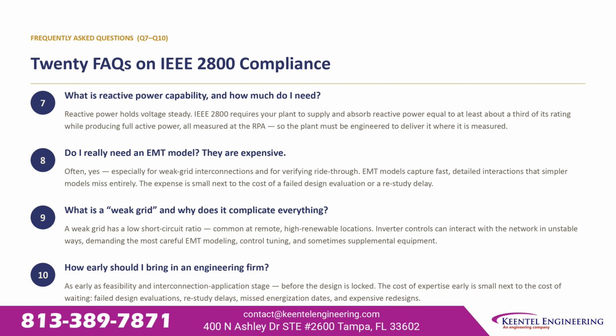What is reactive power capability, and how much do you need? Reactive power holds voltage steady. IEEE 2800 requires your plant to supply and absorb reactive power equal to at least about a third of its rating while producing full active power, all measured at the RPA, so the plant has to be engineered to deliver it right where it's measured. Do you really need an EMT model, even though they're expensive? Often, yes, especially for weak grid interconnections and for verifying ride-through. EMT models capture fast, detailed interactions that simpler models miss entirely. The expense is small next to the cost of a failed design evaluation or a restudy delay.